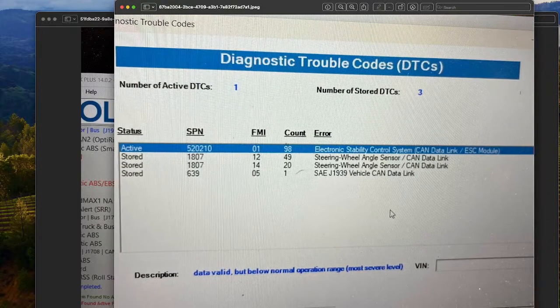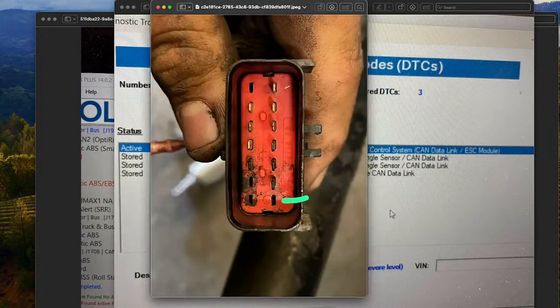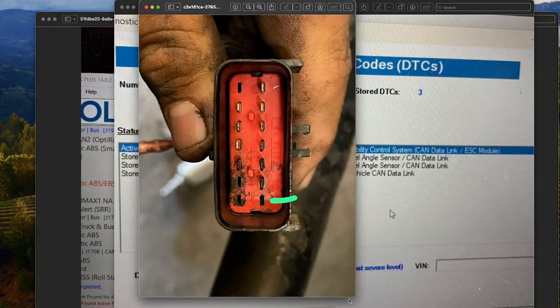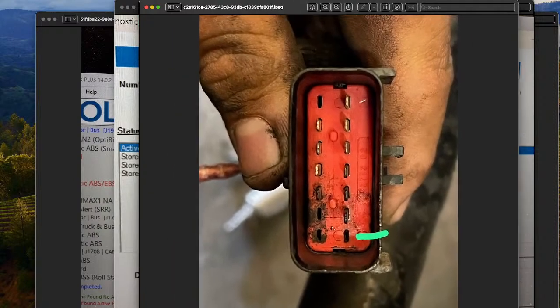Because like I mentioned, if this was an active code and not a data link issue, we would just recalibrate. But the recalibration failed. The next steps involved testing connections and ensuring the data link was intact, and we found an issue in the cable.